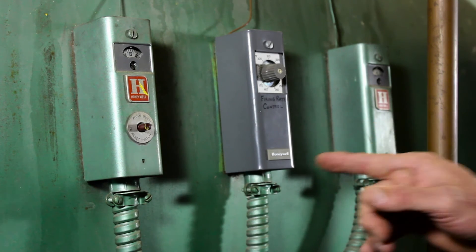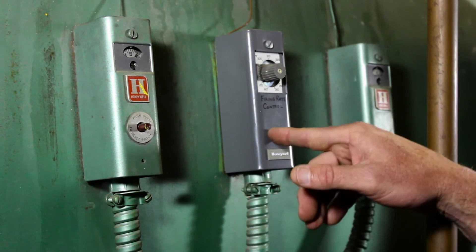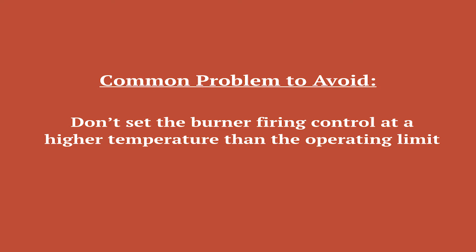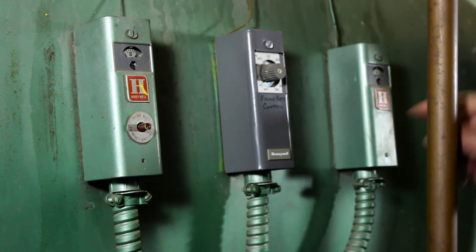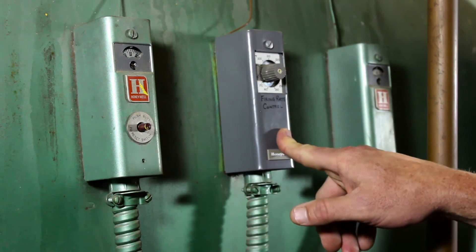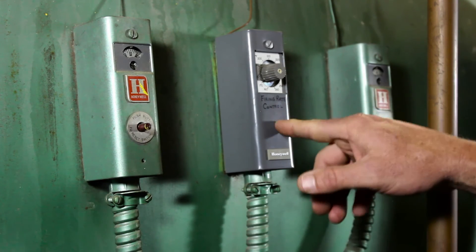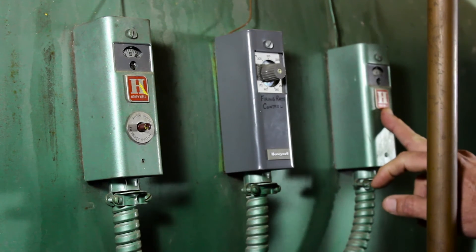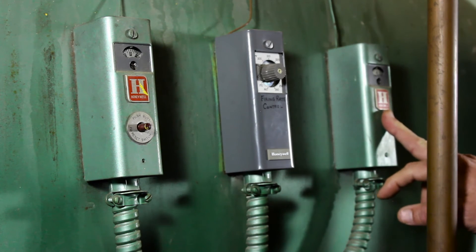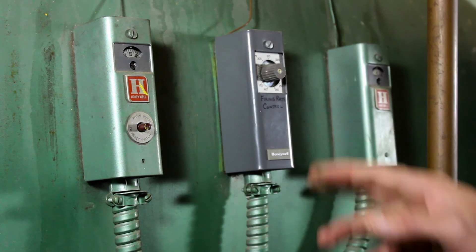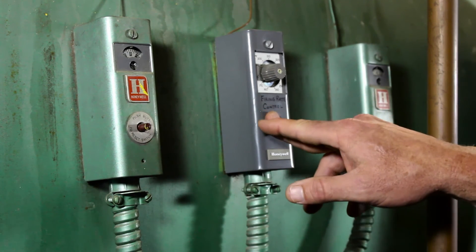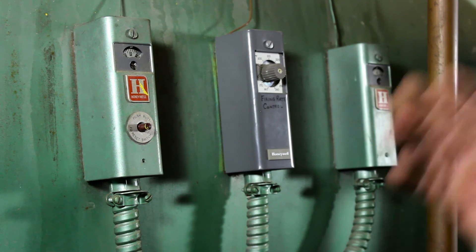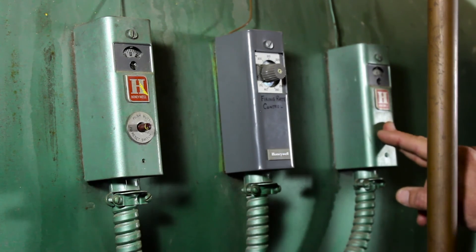One of the common problems: a lot of times people will set this firing rate controller at a higher temperature than the operating limit. What that causes is when the boiler comes on, it tries to control at the firing rate control set point. So if the operating limit is set at 180 and the firing rate was set at 200, when the boiler came on it would try to reach 200. But before it could satisfy the firing rate controller with the burner at maximum fire, it'll hit up against the operating limit and the burner will shut off. Then it shuts off, goes through a post-purge and pre-purge, and immediately when this resets, it thinks it wants to go to 200 again, the burner goes to full fire, tries to get to 200, then hits against this and shuts off again.